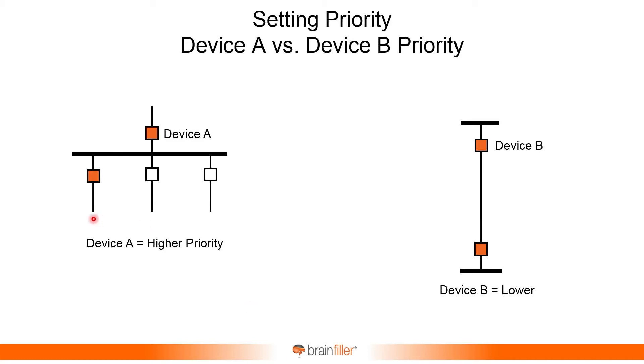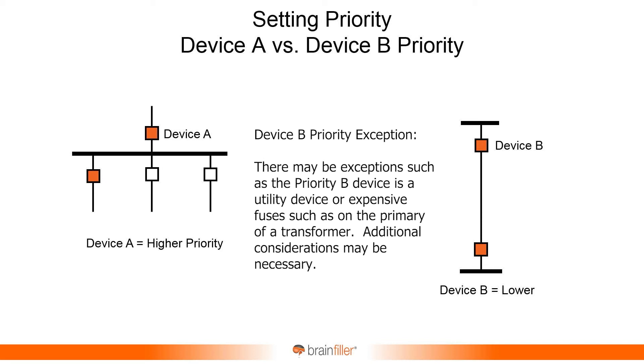If the event is right at the feeder, you want the best coordination possible between the feeder and the main. Because if the main trips, you've not just isolated that one feeder — you've also taken out all the other circuits. That's undesirable; you have a wider-spread outage. Whereas a B priority is where you have one device feeding only one other device. In that case, if either one of those devices trips, you're losing the same load — the same panel.